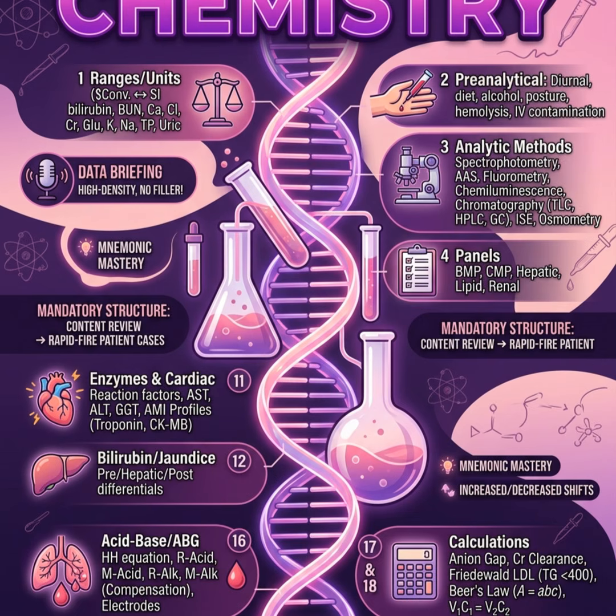Okay, so how does AAS differ from standard spectro? Well, standard spectrophotometry measures light absorbed by molecules in a liquid. AAS measures light absorbed by ground state atoms in a flame. Wow, okay, in a flame. Yeah, and the hardware path is strictly tested. You start with a hollow cathode lamp. What's brilliant about this is that the cathode inside the lamp is literally made of the metal you're trying to measure. Oh, that is cool. So if you are looking for lead, you literally use a lead lamp. Exactly. It emits the exact, highly specific wavelength that lead atoms will absorb.